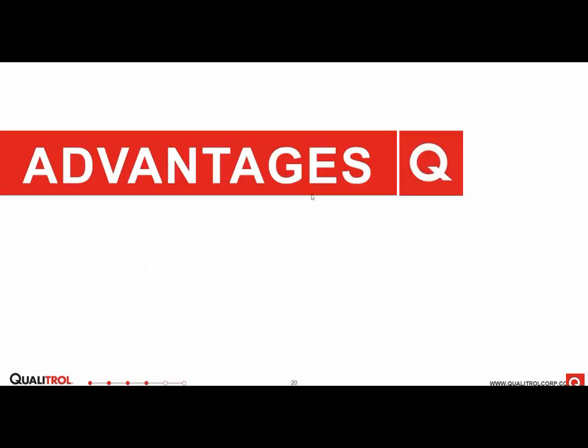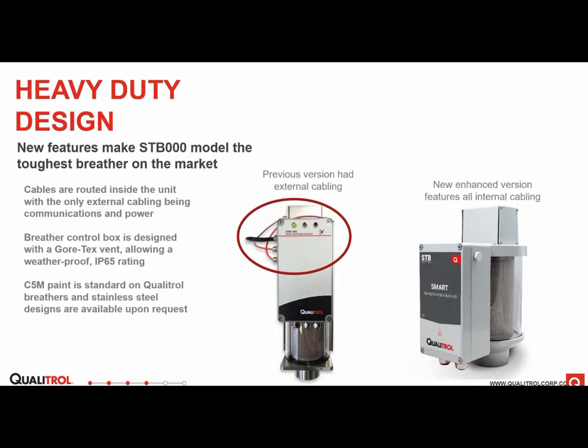So, some more advantages with the new Qualitrol Smart Transformer breather. We really upped the physical design of the breather, based on a lot of great customer feedback. A big thing that everybody wanted was no more external cables. So now we routed all of the cables inside the sensor block into the control enclosure. So there's no more external cabling where it can get caught on anything in the field.